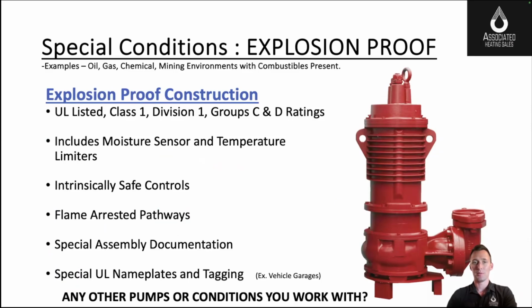And those fluids that are present are combustible. So any sort of spark may cause a fire or explosion within the pit. An explosion-proof pump is built in a way that no spark will leave the pump. Right? So it's UL listed for hazardous environments. It includes those sensors that we talked about to let you know when something's going wrong with the pump. And there are flame arrestor pathways and a special build here to not allow a spark to leave the pump.